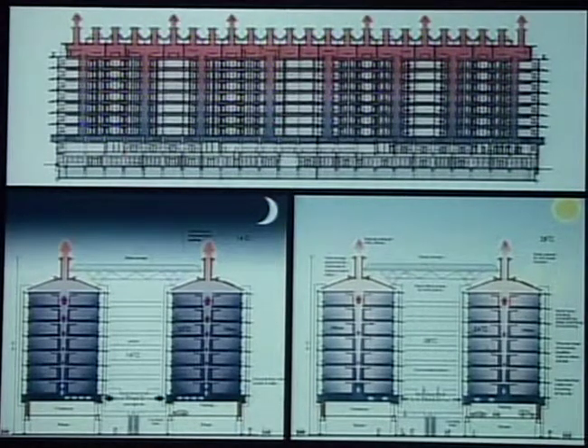And at intervals in the length, which the top section shows, there are chimneys running right through the offices. And they combine at the top level to form real chimneys that stick up above the roof. And what's happening is that at night, the outside air temperature drops down to 14, the inside is still at 25, 26, probably 28. And so you get really good stack effect, which helps the fans.